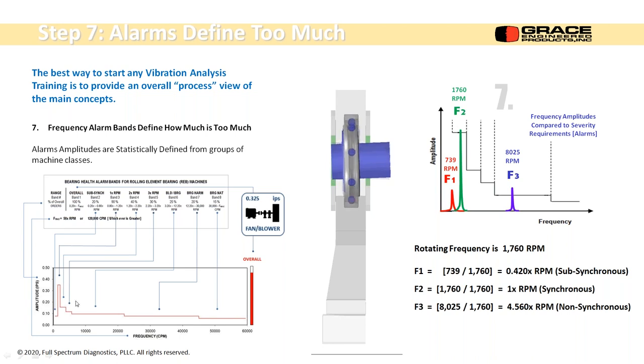The nice thing about the database is you can set your alarms any way you want, and you can set them up to learn so that they'll adjust these levels. These are a good starting point, the 20%, 90%, and so forth. Statistically, you can look at every band, and you can use as many bands as you like. The result is we have frequency amplitudes, and we can compare some severity criteria to them. So I have the stair-step program, and it looks like my frequency at turning speed of the shaft is exceeding that, and at this higher frequency out there. Once you're in a frequency format, you compare everything to the turning speed of the shaft to see what frequency it is. Frequency one, 739 divided by 1760, the turning speed of the shaft, I get 0.42 times RPM.